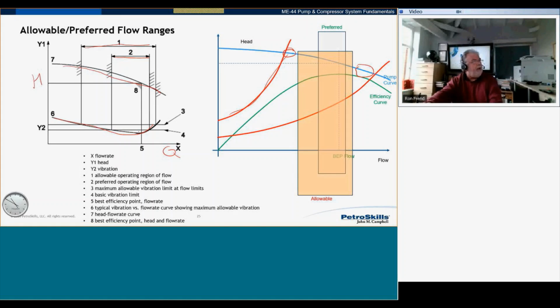At BEP, the vibration coming from the operation is minimal. But as soon as you start operating at other flow rates, you very quickly find the vibration increases, both high flow and low flow. This is well known, it's well documented. Please make sure that you check this when you get your new pump. It's a good idea to make this part of your commissioning process, just to check what your vibration levels are at different flows. And once you do that, you can correlate that to the allowable vibration levels, and you can check what your allowable region is at the very least.